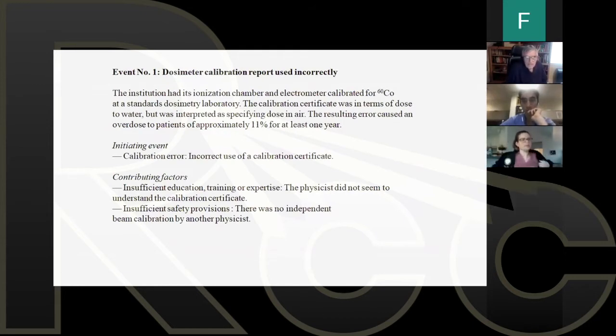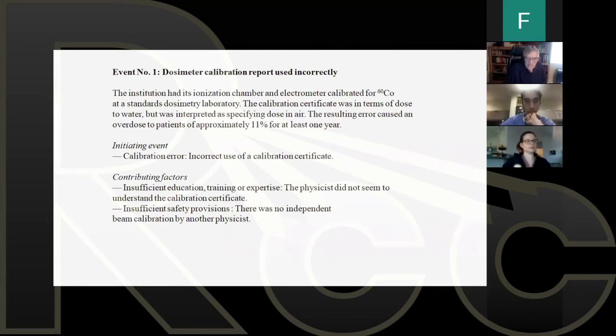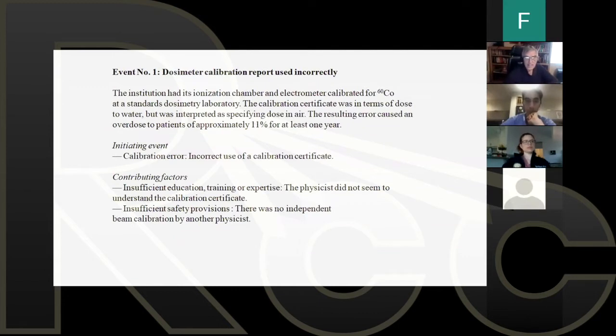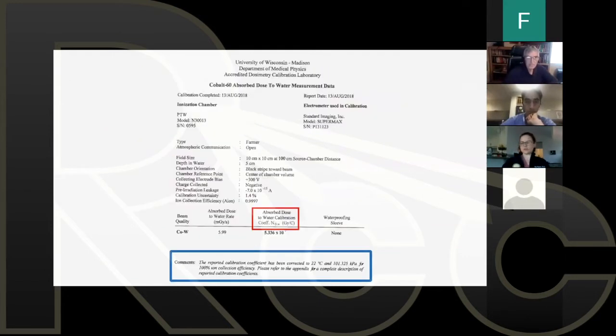The initiating event was an incorrect use of a calibration certificate. And then the IAEA also looks at contributing factors. They determined that there was insufficient education, insufficient training or expertise. The physicist did not seem to understand the certificate. And there was no independent beam calibration by another physicist, or I might even add, by an outside agency, which could have picked this up.